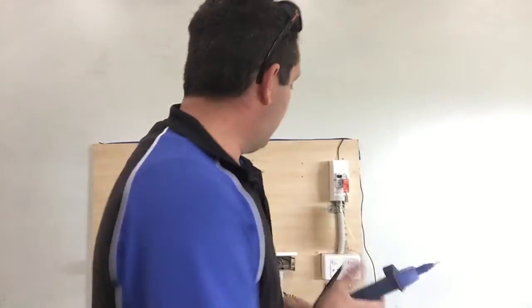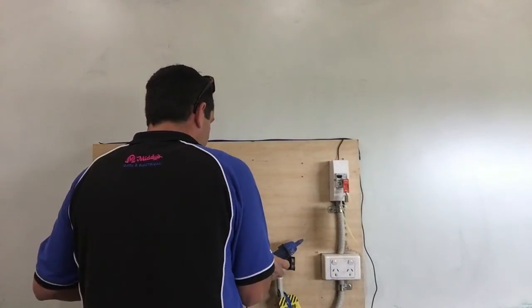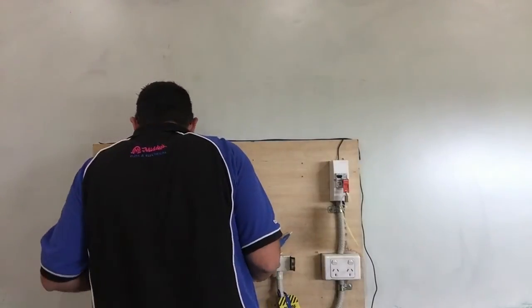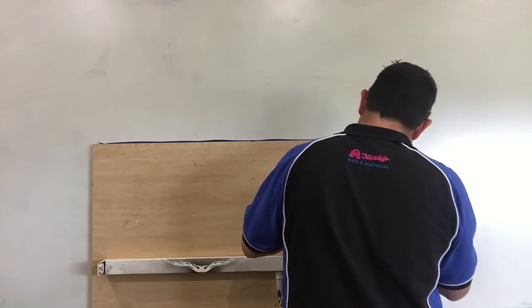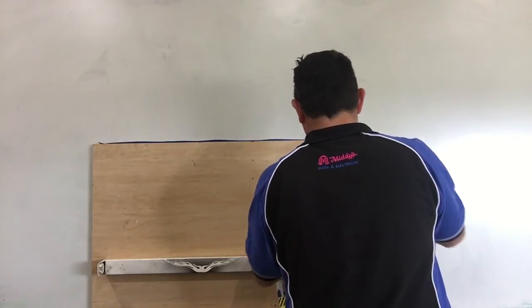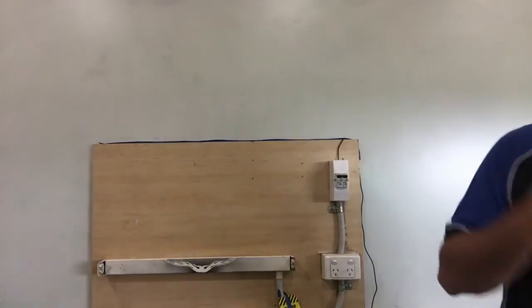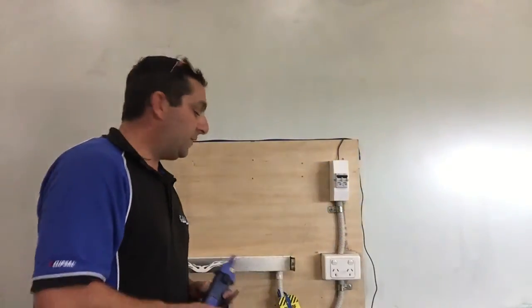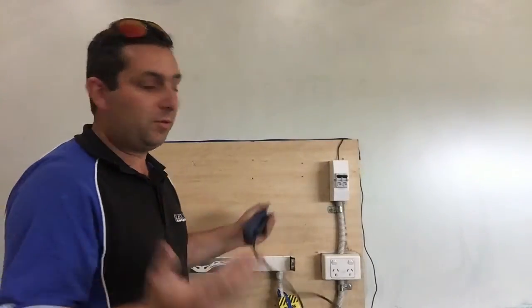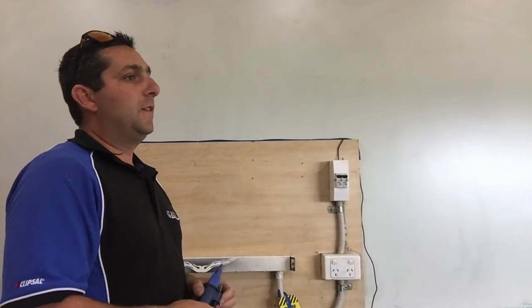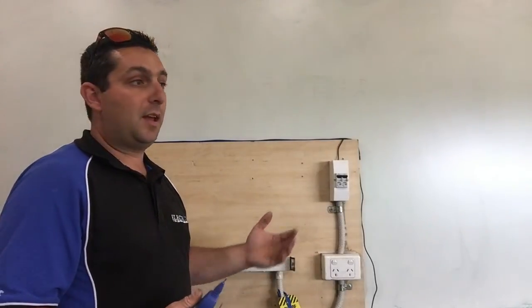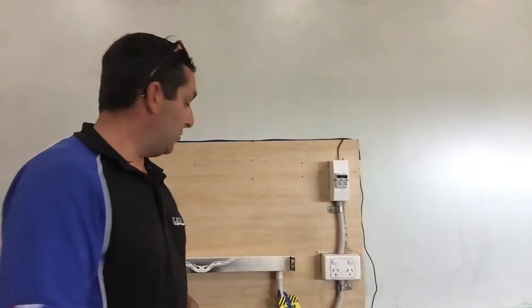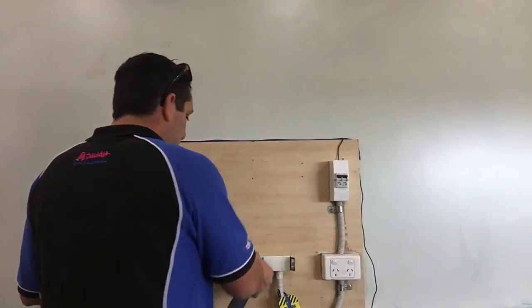Okay, test your meter again. Make sure it's down to 0, which it is. And we're going to put the cover back on the appliance and get ready to re-energise. Okay, we can remove the padlock and our lock, and we can re-energise. And it's fine to re-energise now. We've tested the appliance. We've tested the earthing system, so if there is a fault or there is anything, we know that the path for that fault current has a low enough impedance to ensure that our circuit breaker would trip. Okay, now that we've done that, remove the cover.